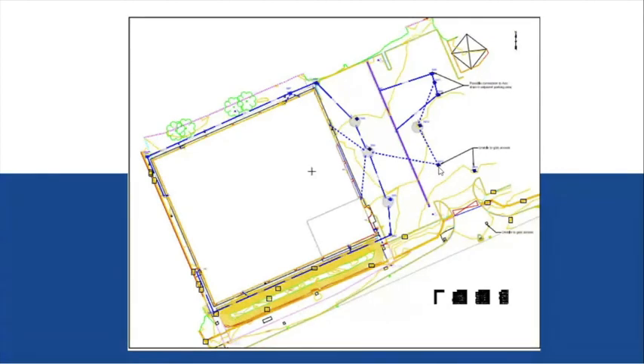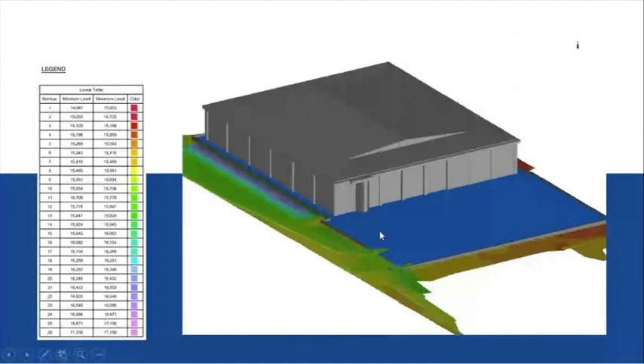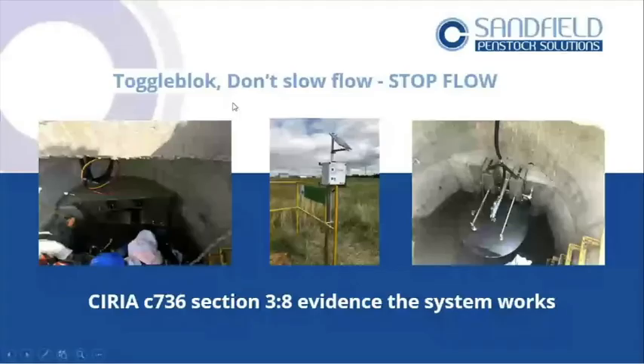This site without doing anything to the drainage network already has a reasonable amount of containment. Looking at the site as it stands, there's no wall in places — they're going to need to build a wall. The driveway in is the lowest point, so a tabletop may need to go there — but remember tabletops with support lists and some vehicles can cause issues. If the EA requires a 24-hour firewater containment plan, some significant structure around the site will be needed. That cost can now be assessed before going any further into the actual build.